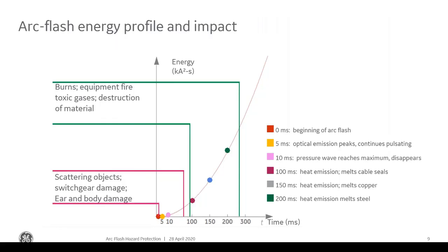Now, what is the damage mechanism and how does it develop? As I mentioned, it develops very, very quickly. The optical emission happens right after the onset of the arc flash. In this slide, at about 0 milliseconds is where the arc flash starts, and at about 5 milliseconds the optical emission peaks, and it continues to pulsate, generating all of the energy for the arc flash incident energy.